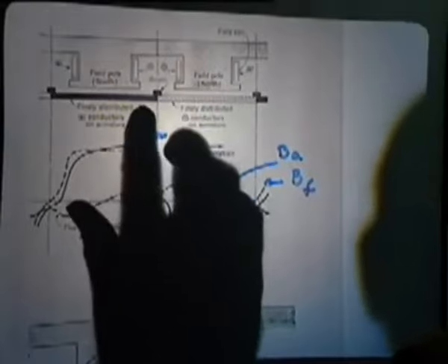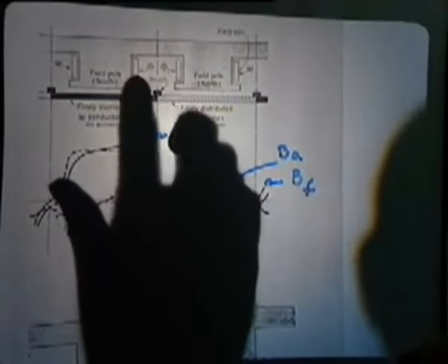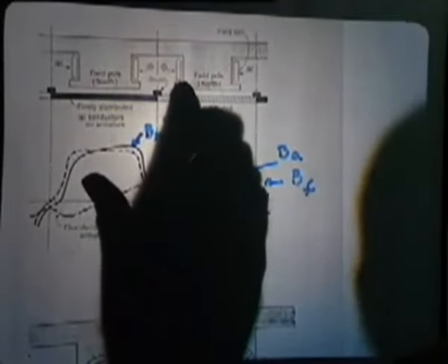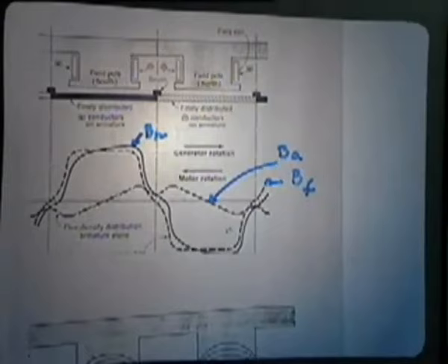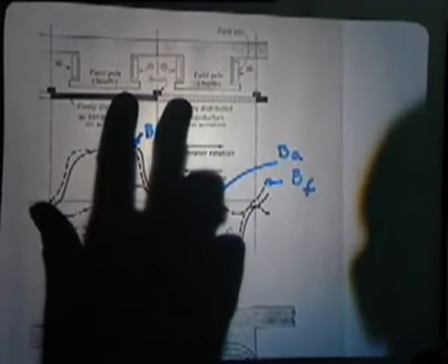That means you have in the armature during this region the armature teeth, and also the pole tips. If they are more saturated in the pole tips, it will increase the reluctance. Okay. And so one of the methods is to try to increase the reluctance in the interpolar region by driving them into saturation.